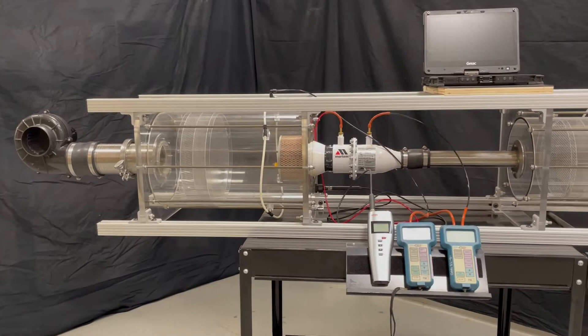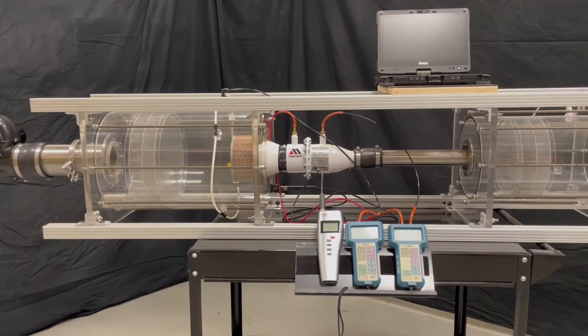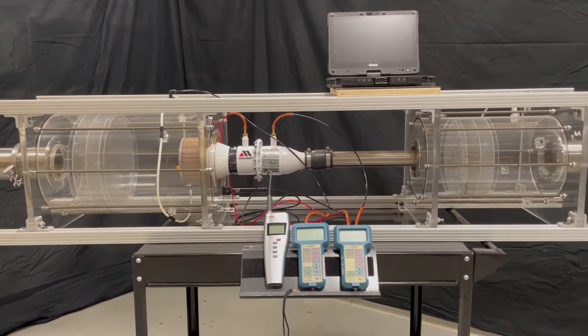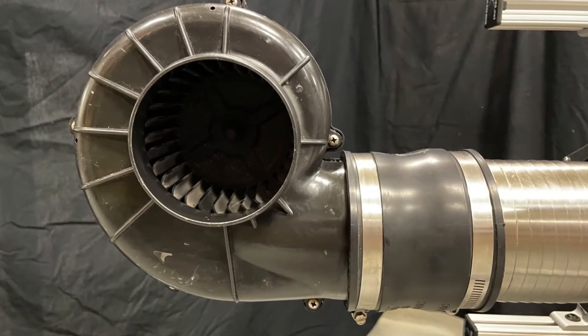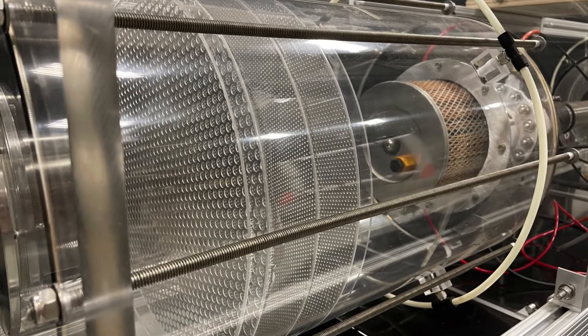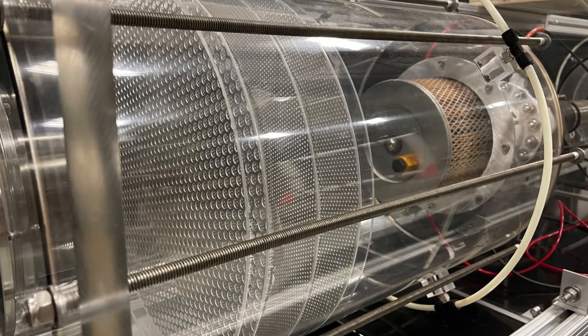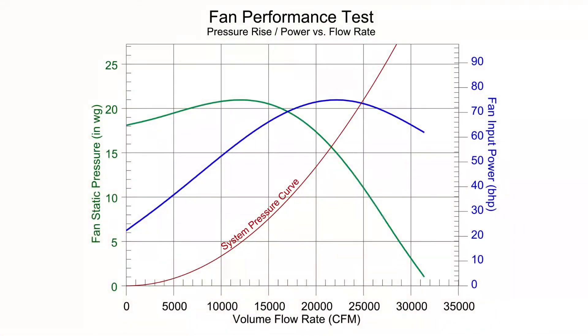So can you tell me what a typical test looks like? Absolutely. Here's an example of a flow tunnel measuring fan performance. The fan is connected by a duct to the flow tunnel, as shown. This allows you to set the fan to a range of settings — high, medium, low, or a specified voltage or even pressure rise. Then the flow tunnel very accurately measures the flow from the fan. If you test at several different fan settings or pressures, you can then create a fan curve. This is an essential specification sheet used by fan manufacturers to denote the performance characteristics of the fan.